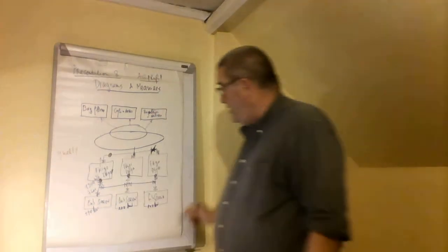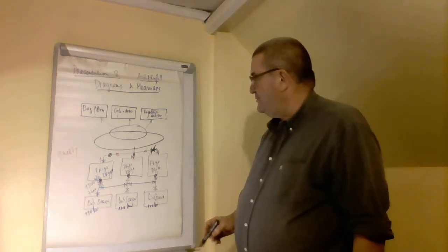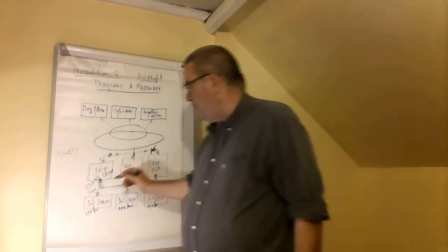So here you have a problem of quality. You may have to measure the flow by means of Venturi pipes on each of the outlets to make sure that they work, and that you don't have too big a flow here, which would be the cause of a lower quality, of a higher pressure dew point. This is one thing that you can have.